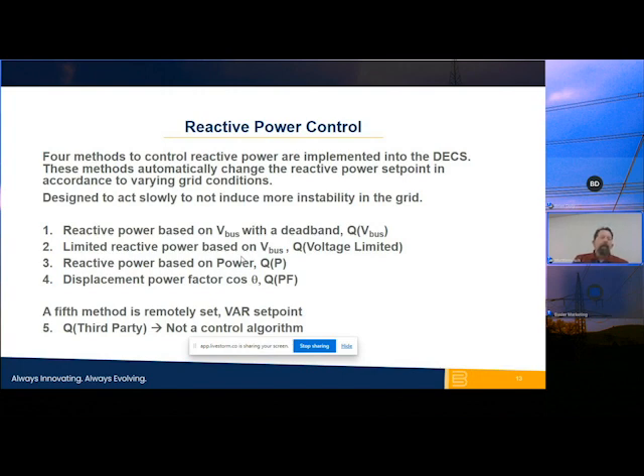And then there is a fifth method, which is what we call the Q third party. It is not a control algorithm within the DECS product. What it really is, is a remote set point. So to maintain the grid control and the reactive power component at the point of common connection, we can use a third party device. This could be an overall SCADA system, a grid operator set point, or remote set point control. But it's going to provide basically a fixed reactive power set point from some external device. And these would come through the auxiliary inputs of the DECS products, or the use of an AEM 2020 analog expansion module.